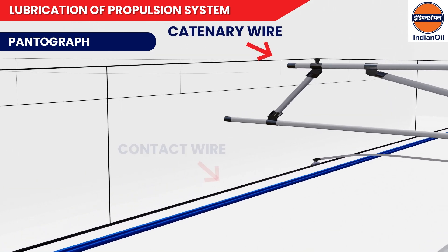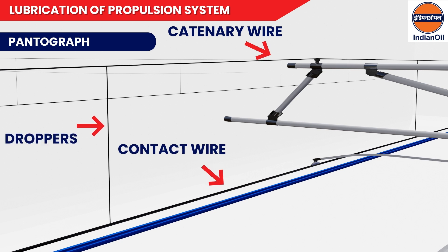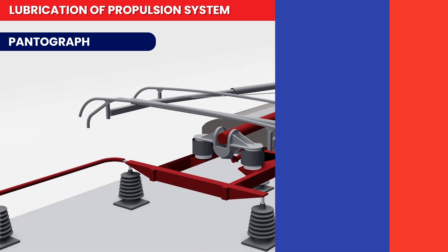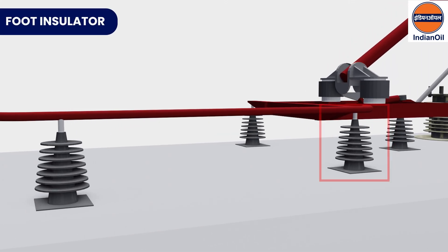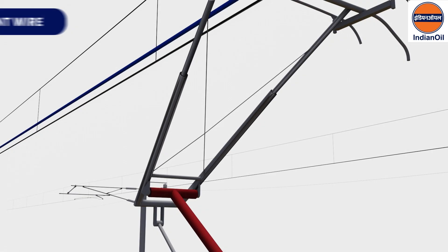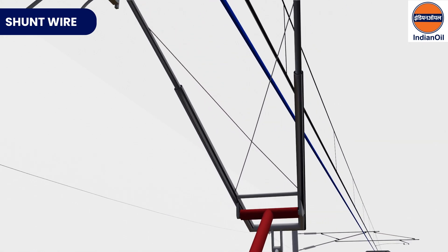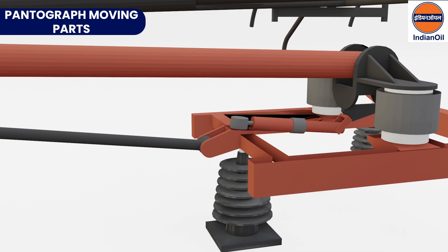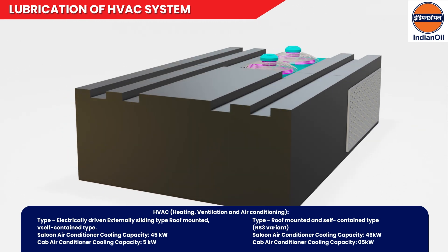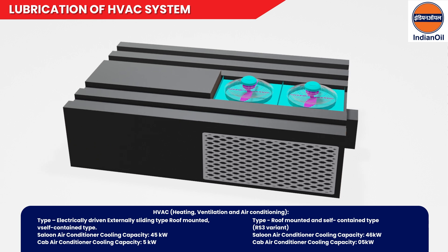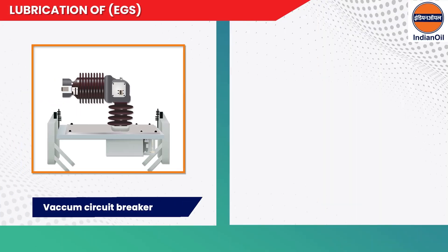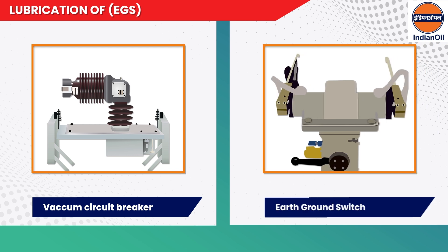Lubrication for the propulsion system is applied as: grease used on gear of master controller and for bearing of traction motor; a thin insulating coating on the foot insulator of the pantograph; conductive grease on shunt wire of pantograph, pantograph moving parts and bearings, and contactor HV contacts. For HVAC (heating, ventilation, and air conditioning): refrigeration oil is used for the HVAC compressor. Number four: earth ground switch — grease is applied for VCB (vacuum circuit breaker) and EGS moving contacts.